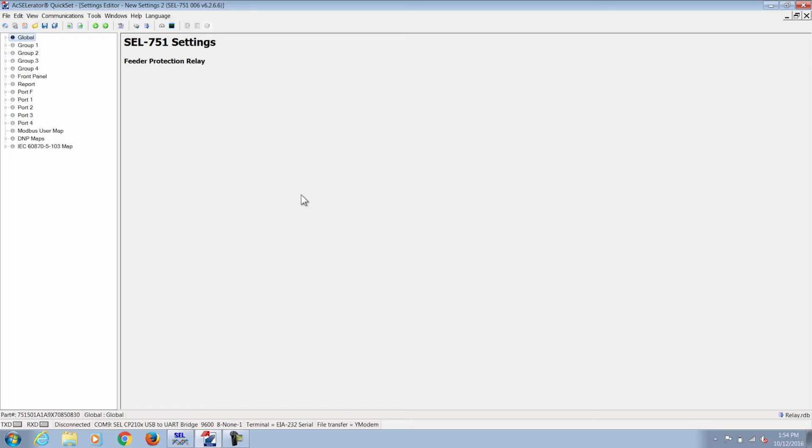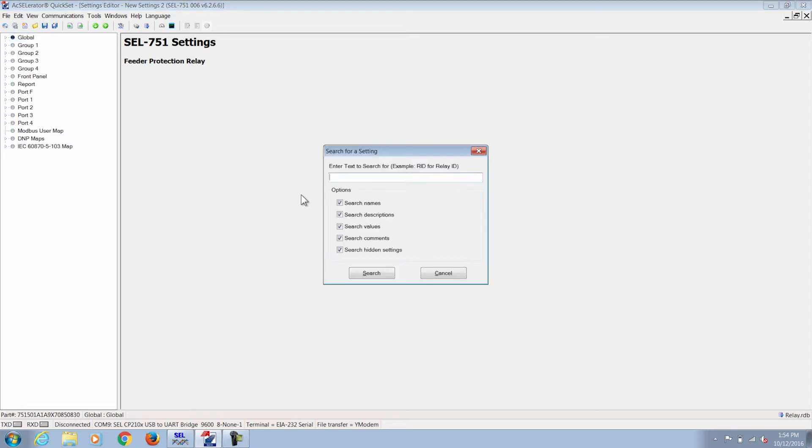In particular, what we're going to talk about is setting a 50 and a 51 relay, which are fairly common protection elements to replace an electromechanical relay with. Now to do that we can do a Ctrl+F and search for the particular setting that we're trying to program.